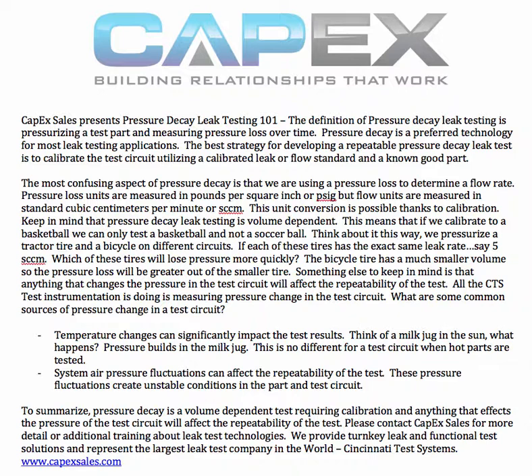The bicycle tire, because it is much smaller and has a much smaller volume than the tractor tire, is going to lose pressure much more quickly. So again, just trying to give you a visual on why pressure decay leak testing is volume dependent and how important it is to maintain the same volume for pressure decay leak testing.